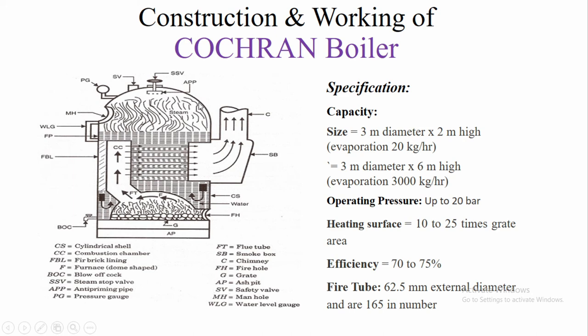At the top surface of the crown there are several valves and instruments: a safety valve, steam stop valve, pressure gauge, water level indicator, and fusible plug. These are the boiler mountings used for the safety of the boiler. There is also an anti-priming pipe which separates water and steam, allowing only steam to flow through the steam stop valve.